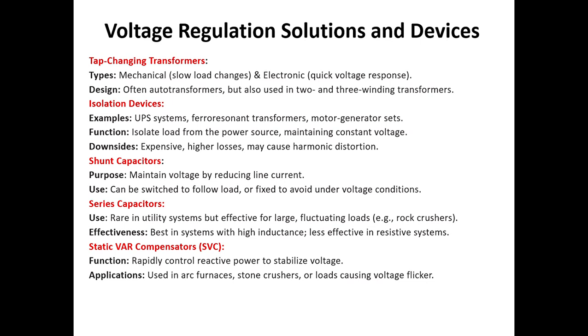Now the static VAR compensators. Again, this is a FACTS device. FACTS means flexible AC transmission system. It rapidly controls the reactive power to stabilize the voltage. Applications include arc furnaces. We can also use it with stone crushers or loads causing voltage flicker. So these are different devices that we can use for voltage regulation purposes.